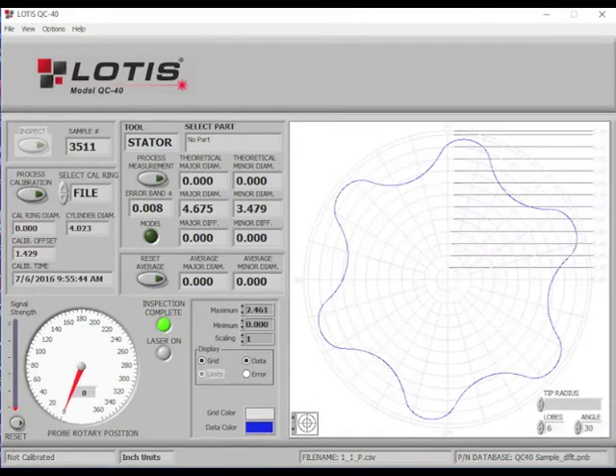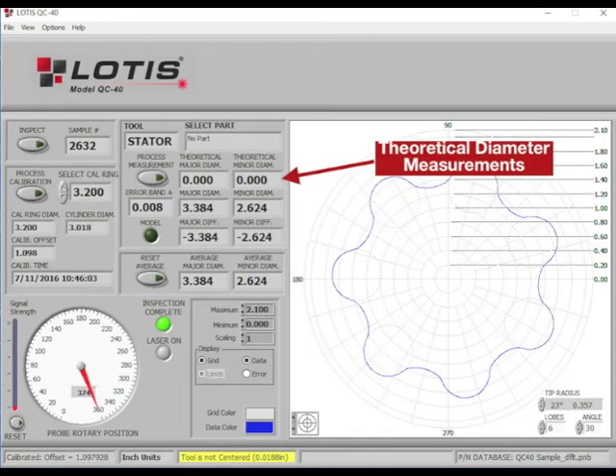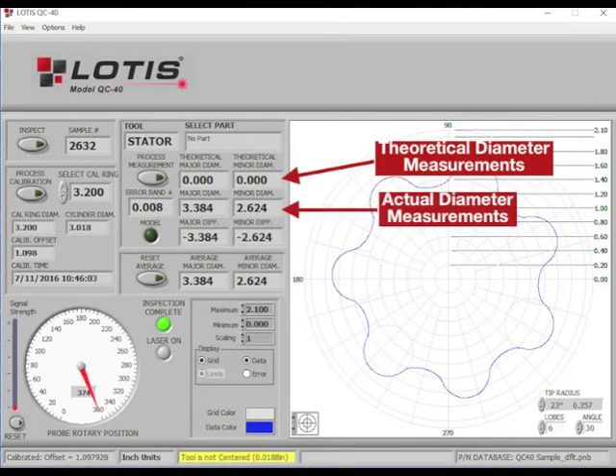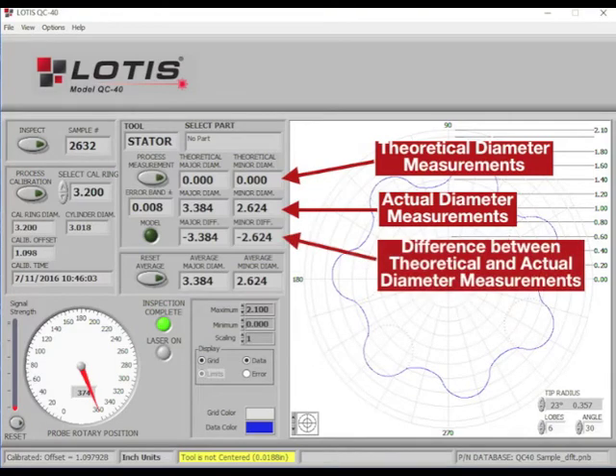Full profile scans are the only way to catch issues such as this to prevent non-production time on the rig. This product verifies full profile instead of just the minor diameter, measures tip diameter, flank data, major and minor diameter, and provides information on wear with an accuracy of two thousandths of an inch.